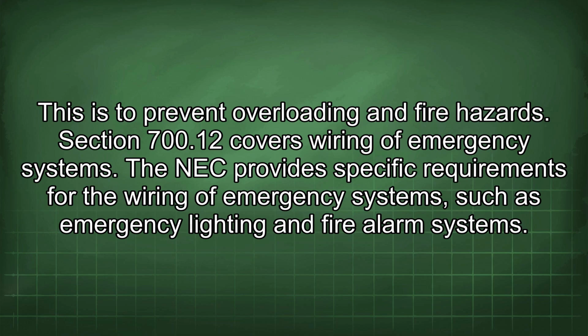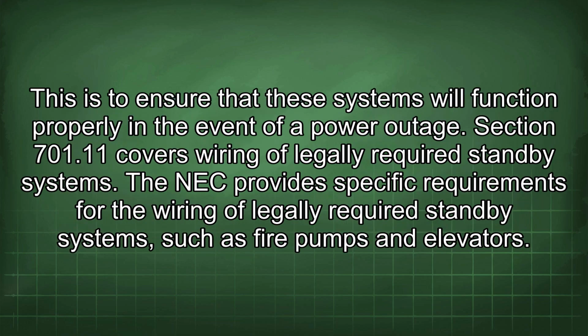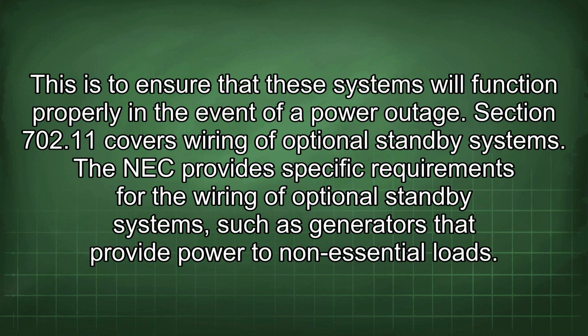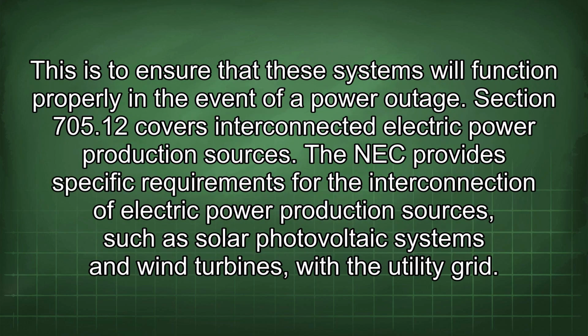Section 700.12 covers wiring of emergency systems. The NEC provides specific requirements for the wiring of emergency systems, such as emergency lighting and fire alarm systems. This is to ensure that these systems will function properly in the event of a power outage. Section 701.11 covers wiring of legally required standby systems. The NEC provides specific requirements for the wiring of legally required standby systems, such as fire pumps and elevators. This is to ensure that these systems will function properly in the event of a power outage. Section 702.11 covers wiring of optional standby systems. The NEC provides specific requirements for the wiring of optional standby systems, such as generators that provide power to non-essential loads. This is to ensure that these systems will function properly in the event of a power outage.